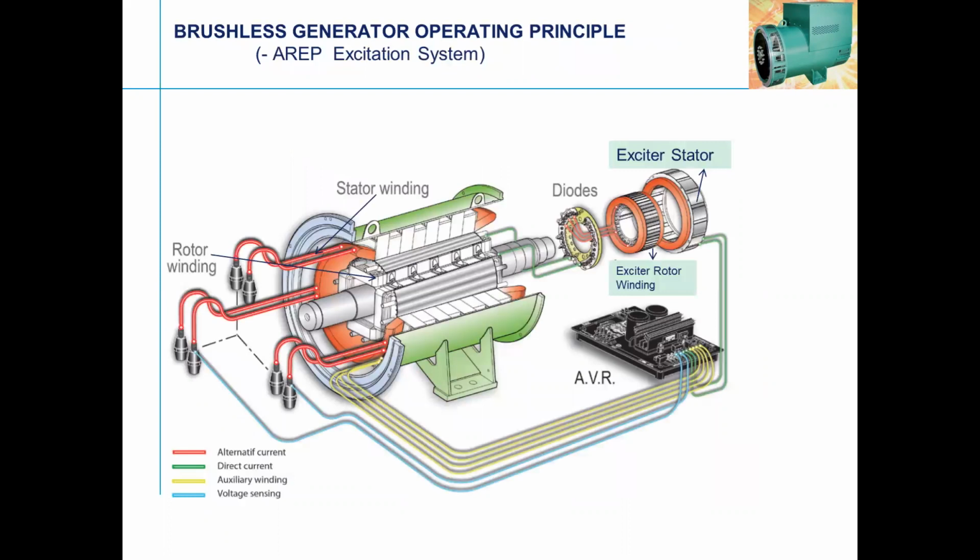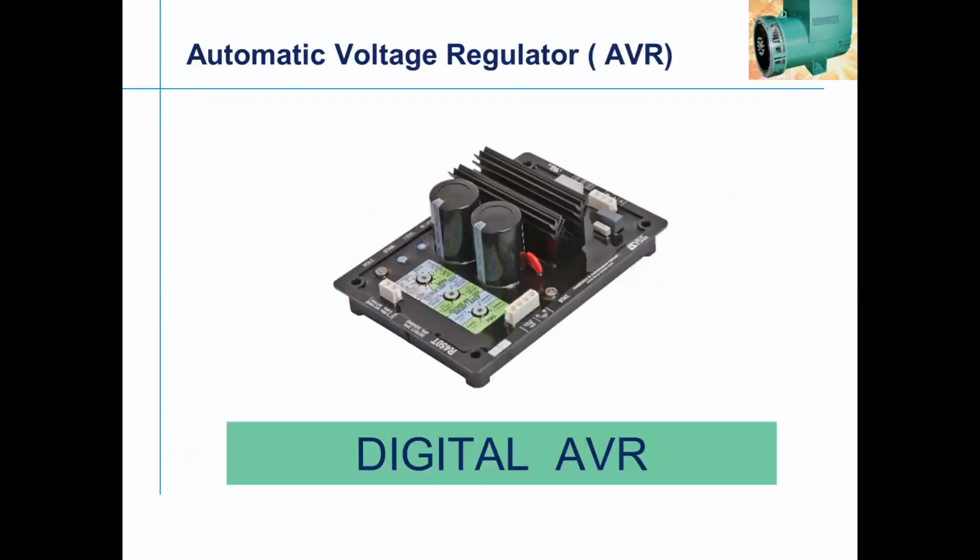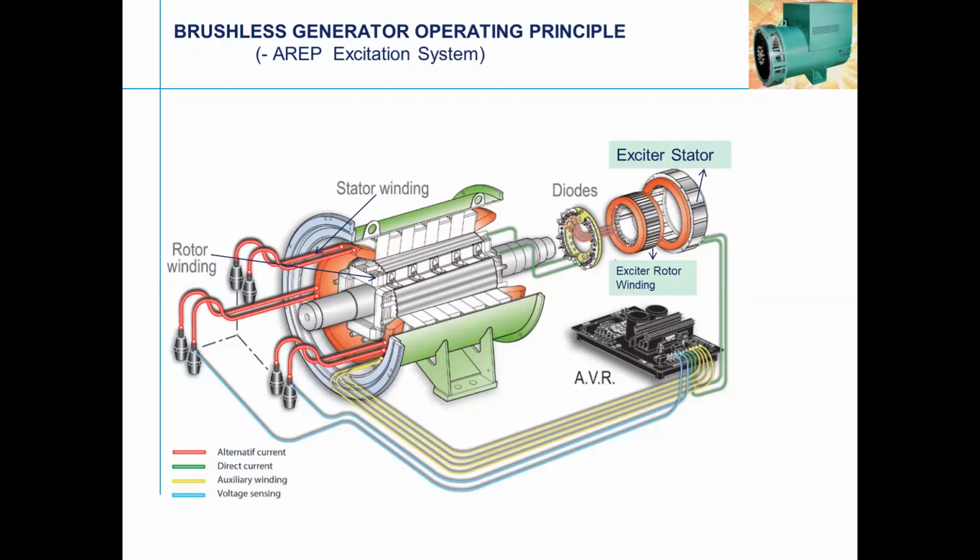Okay, coming to this RF, maybe RF AREP, this has been fundamentally called auxiliary regulation excitation principle. Of course, this is a patent of Leroy Somer. You can see this winding where the cross-functional. Instead of the 3-machine system, here you will see the 2-machine system, but the RF will be 2 winding. That means X1, X2, one is voltage winding and current winding, which is given in the main stator itself. So that will be feeding the AVR.